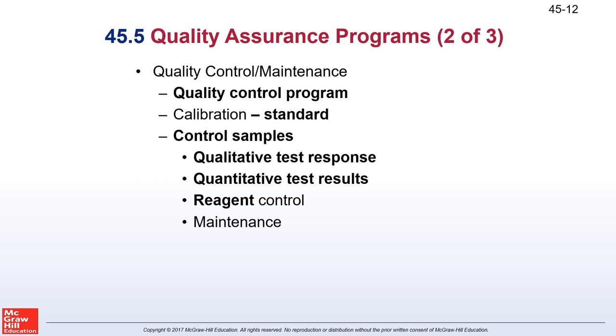So a couple things—as mentioned, your equipment needs to be calibrated. For that glucose meter, one thing you can use is water as your standard. You use water, shine the light, and the device detects how much light bends. Then you put on your sample, and it references how much the light bends with sugar against how much the light bends with just water. That is your standard. Some equipment requires you to use your standard every time you use it; sometimes you only calibrate at the beginning of the day or shift, and you're done.